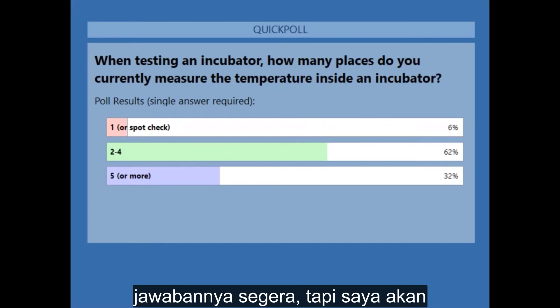So probe placement in general when testing all these parameters, especially temperature and airflow, is really important. And there are common misunderstandings when testing and performing preventive maintenance on infant incubators when it comes to this. Sensors for all of your parameters, including temperature, humidity, airflow, and sound, should be 10 centimeters above the mattress, which is approximately the height of an infant when they're laying flat on the mattress in the incubator. And in terms of numbers, you can see from the image that we're looking for 5 sensors placed at a specific height. So to jump into temperature, which is air convection temperature, and the other thing is airflow, all of those should be measured in those 5 locations inside the incubator. So capturing the temperature in a single location is not acceptable.